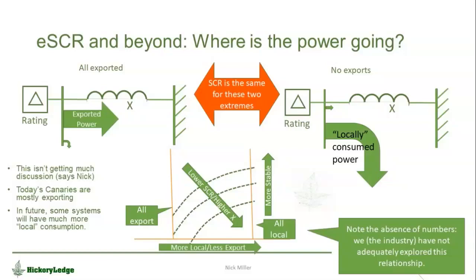Those two drawings, using the way short circuit is calculated, are exactly the same. But on the right-hand side, that system is more stable. The angles and the sensitivity to perturbations for the system with the converters on the right-hand side is lower. That is, it has better ability to follow perturbations. It is less likely, less prone to have the voltage move in such a fashion that the phase lock loop can't keep up with it.